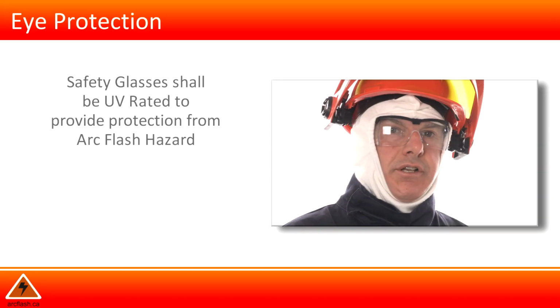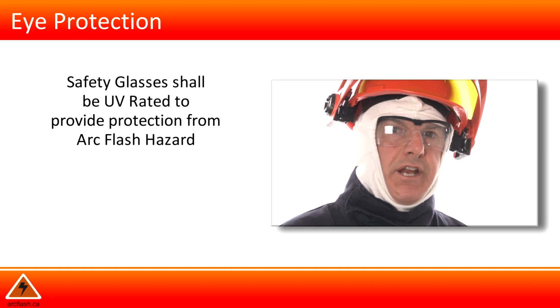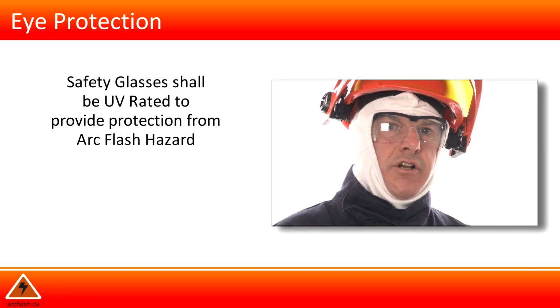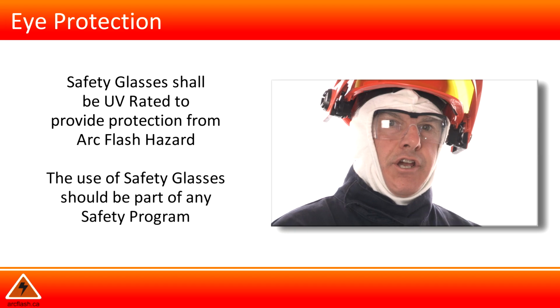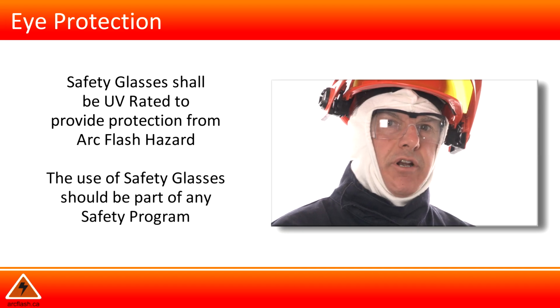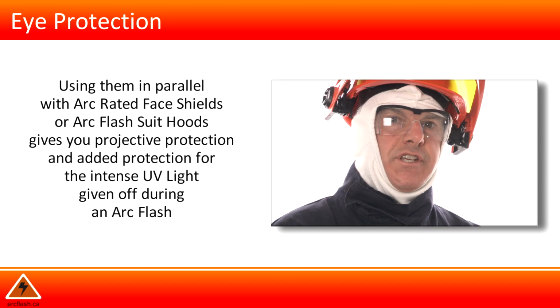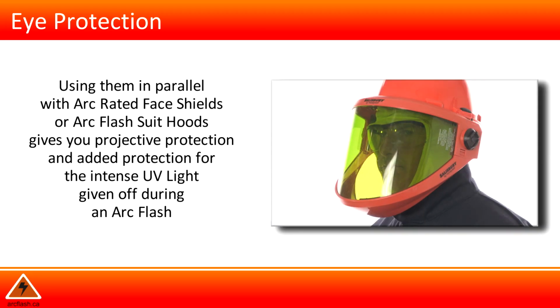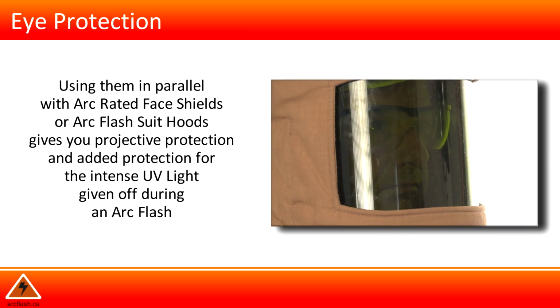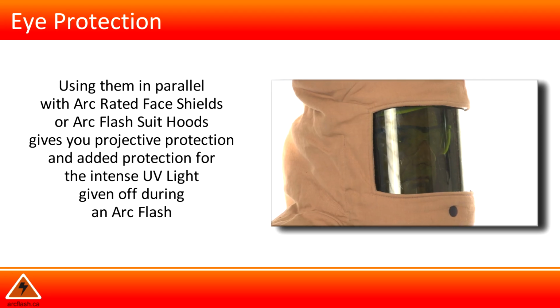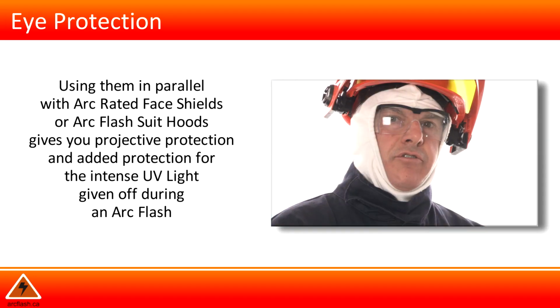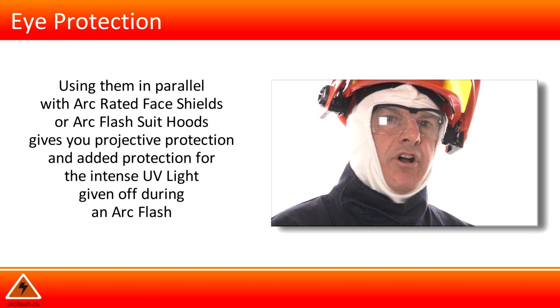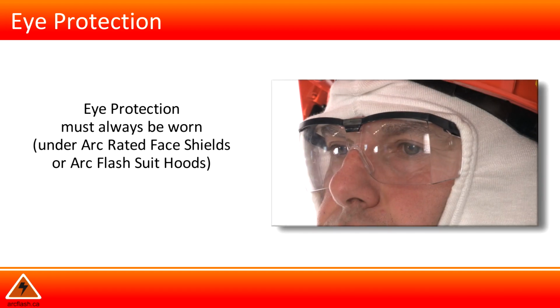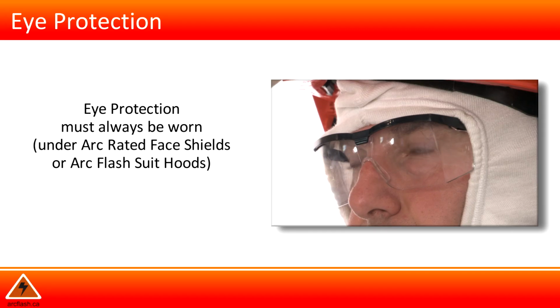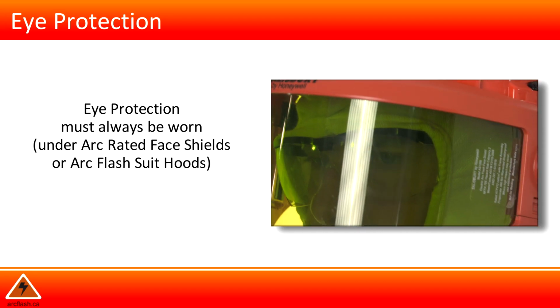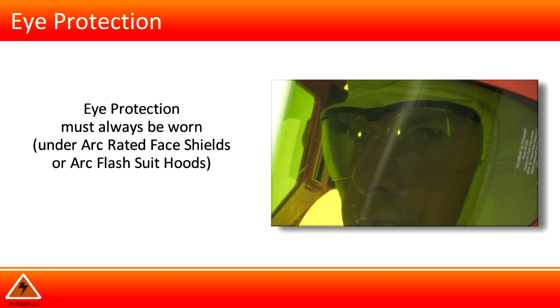Eye protection. Safety glasses shall be UV rated to provide protection from arc flash hazard. The use of safety glasses should be part of any safety program. Using them in parallel with arc-rated face shields or arc flash suit hoods can give you protective protection and added protection for the intense UV light given off during an arc flash. Eye protection must always be worn under arc-rated face shields and under arc flash suit hoods.